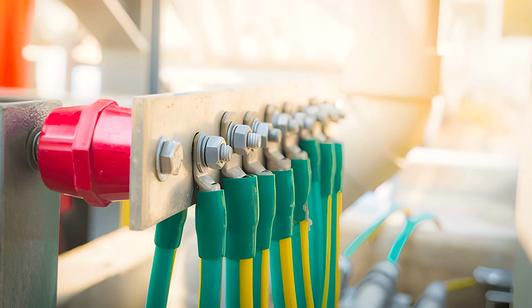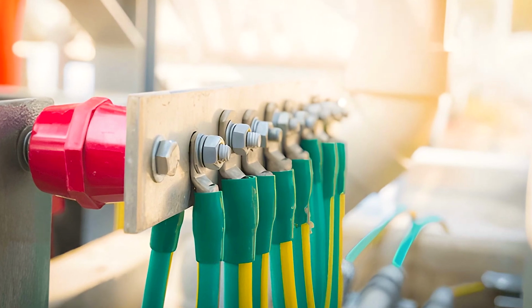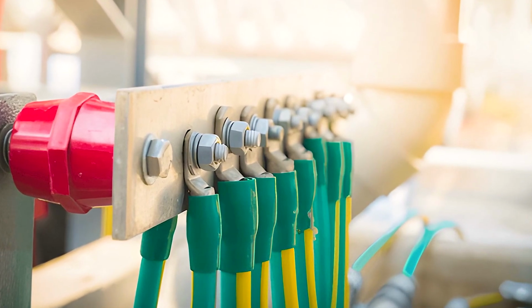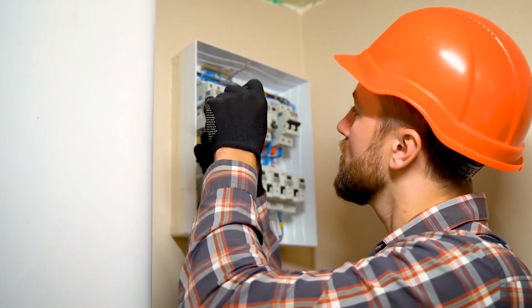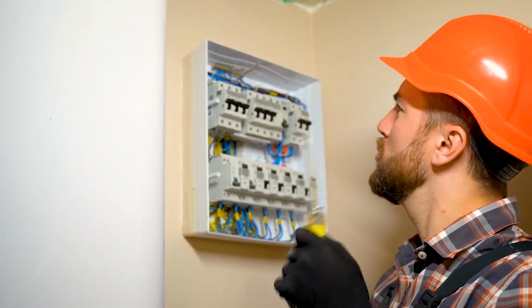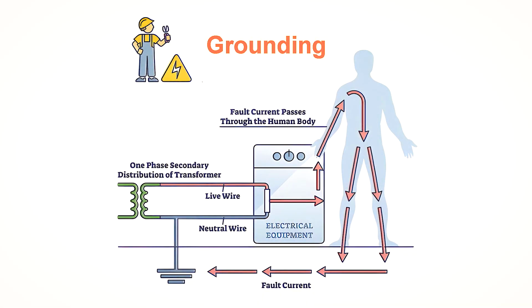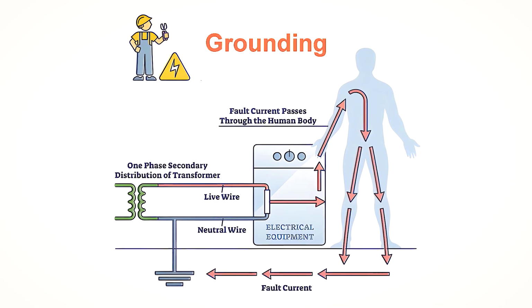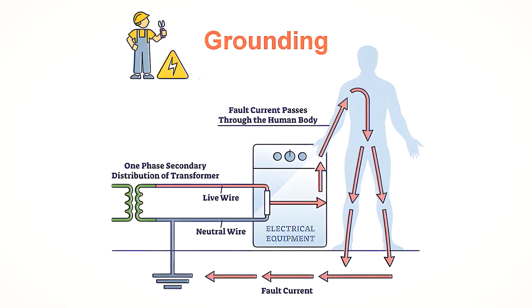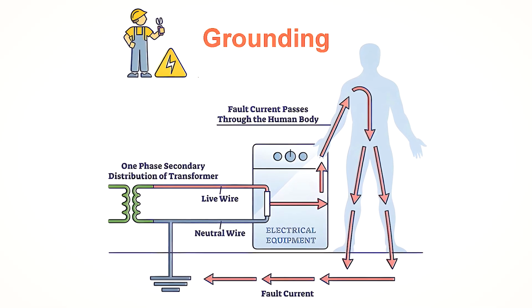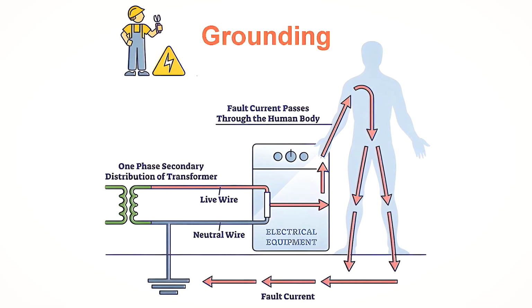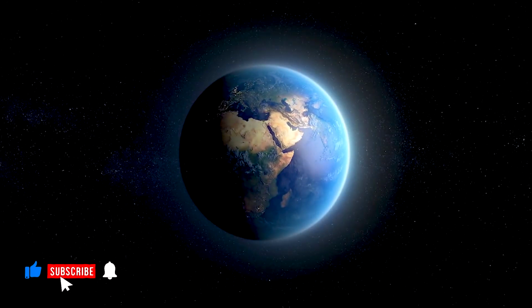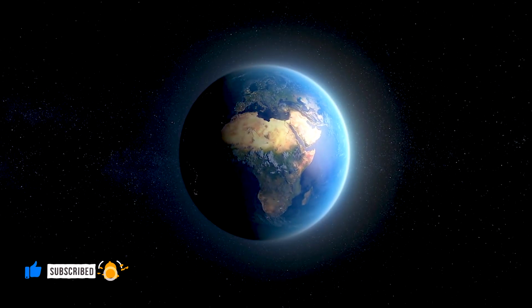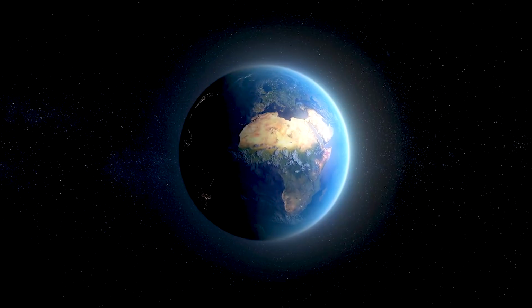Grounding, also known as earthing, is one of the most critical yet often overlooked elements of electrical safety, playing a direct role in protecting human life, electrical equipment, and entire power systems. At its core, grounding is the intentional connection of electrical systems and exposed conductive parts to the earth through a low-resistance path. The earth acts as a vast electrical sink that can safely absorb excess or fault current.